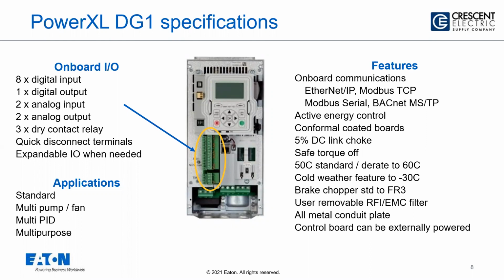It may not be the easiest to see, but there's a plate that goes over those 9 terminals at the bottom. So that's going to separate any of your higher voltage, so your 230, 460, 575, from your lower voltage, which will be up where the yellow circle is, which will be all your 24 volts.